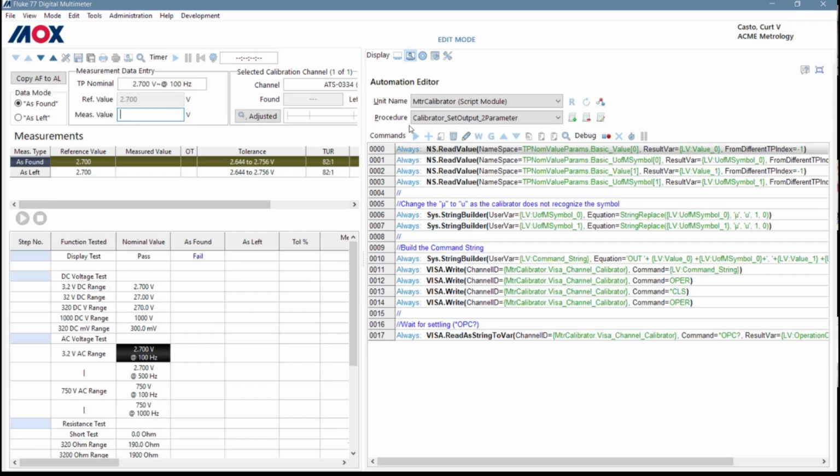See, I like this because I don't have to write that out, right? You already have that command. I select the command and then I can select the next command. It's in the wizard. Right, Alex, when you're dealing with doing this kind of stuff, you actually have to understand how to write some kind of coding, right? Yeah, you had to have the commands where they're using MET/CAL. I mean, you're practically writing code to get it to do what it needs to, and you're hard coding those test points in there too.